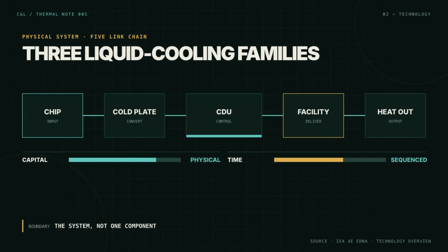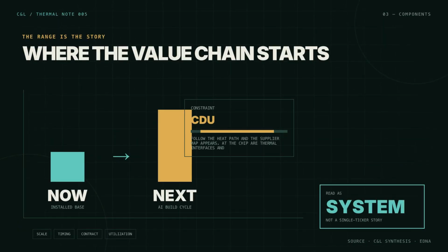The report describes three main families. Direct-to-chip cooling mounts cold plates on hot components and circulates liquid through the server. Immersion cooling submerges equipment in dielectric fluid. Rear door heat exchangers capture hot exhaust at the rack. Direct-to-chip single-phase systems are currently the most mature and widely deployed, representing about 43% of liquid cooling market revenue in the report's assessment, while immersion is the fastest-growing segment. Each design changes who supplies the equipment, how facilities are built, and whether an existing server room can be retrofitted without a complete redesign. Follow the heat path and the supplier map appears.